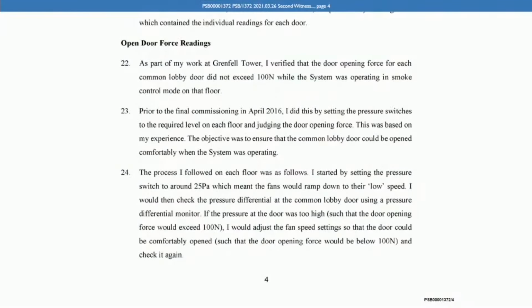And if we look at paragraph 24 of your second statement, page 4, what you're describing here is what you were just describing. Yeah, we did that on every level. So at 23, I think, is the paragraph. You say, prior to the final commissioning in April 2016, I did this by setting the pressure switches to the required level on each floor and judging the door opening force based on my experience. Somewhere in your statement you also say that prior to the final commissioning, you checked the pressure differential in the common lobby door using a pressure differential monitor. The next part down, 24.